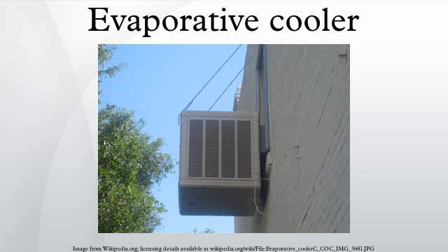Comfort. The air supplied by the evaporative cooler is typically 80–90% relative humidity. Very humid air reduces the evaporation rate of moisture from the skin, nose, lungs, and eyes. High humidity in air accelerates corrosion, particularly in the presence of dust. This can considerably shorten the life of electronic and other equipment. High humidity in air may cause condensation of water. This can be a problem for some situations.